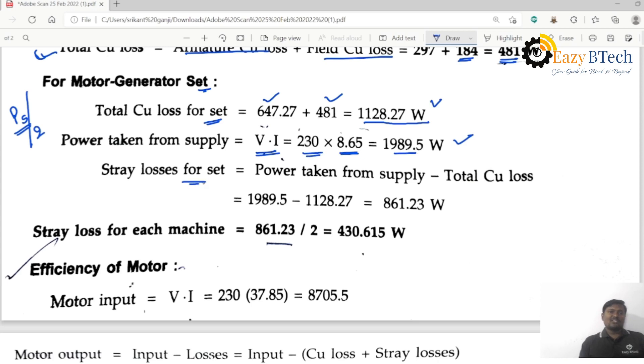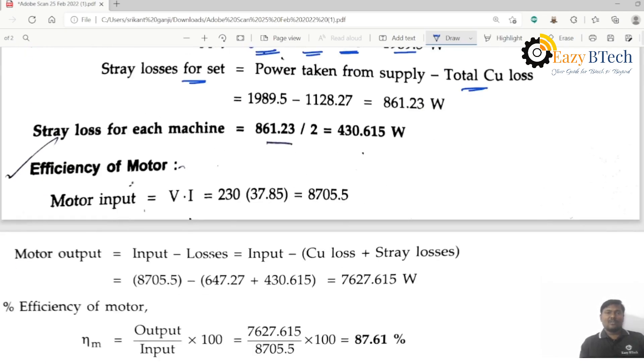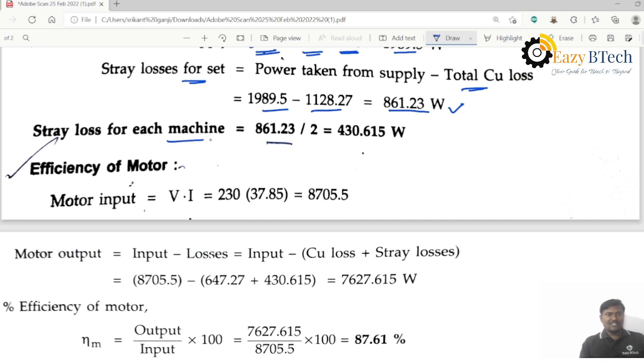Stray losses for the set equals power taken from the supply minus total copper loss: 1989.5 minus 1128.27 equals 861 watts. The stray losses for each machine is then divided by two.